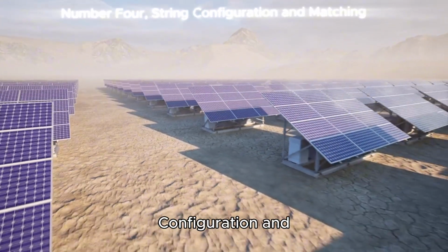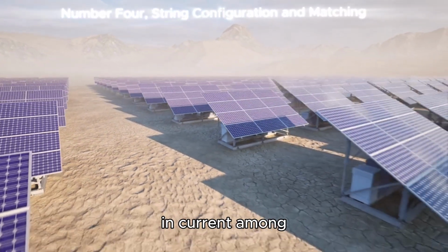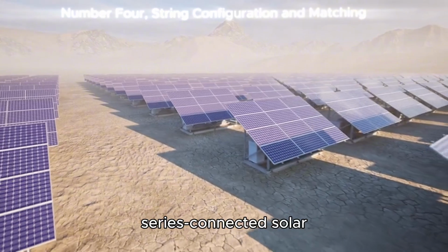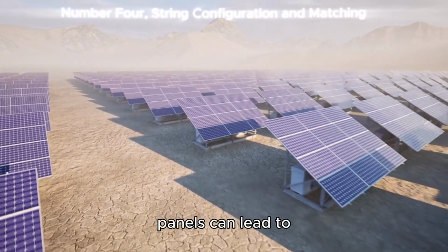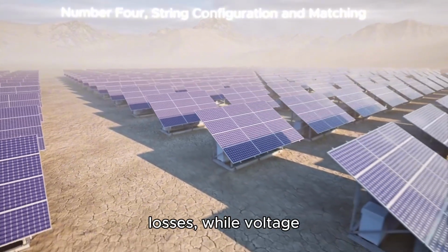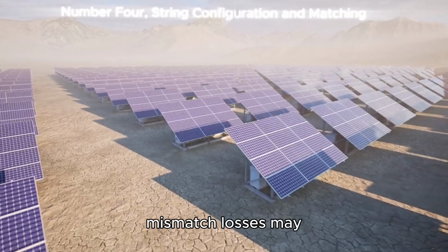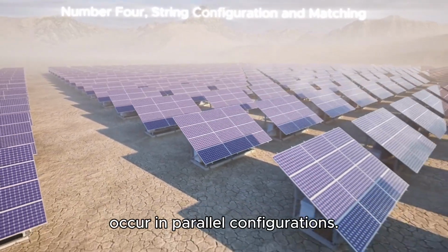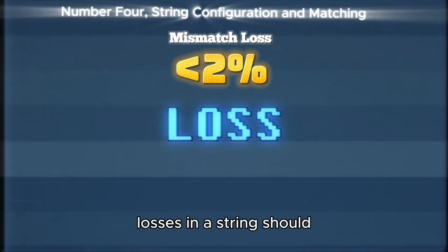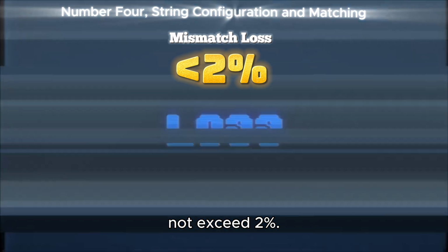Number 4. String configuration and matching. Differences in current among series-connected solar panels can lead to current mismatch losses, while voltage mismatch losses may occur in parallel configurations. Ideally, current mismatch losses in a string should not exceed 2%.